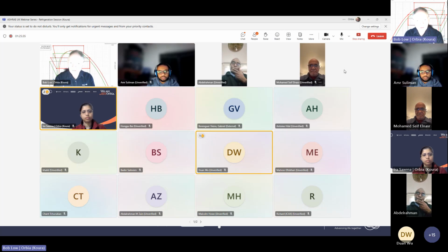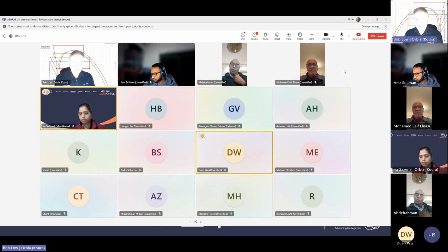The 485A refrigerant has the same sort of lower operating temperature range, about minus 70 C, as 473A does. However, when you look at the compressor characteristics, it would run the compressor extremely hot. So it would require liquid injection cooling, which would take some COP and some capacity away. So although it's attractive, and we are working with one company that's looking at it for minus 70 C, we know quite a few system changes would be needed compared to the current ULT technology, which is basically a cascade of R23 in the bottom or R508 in the bottom into something like R448 or R452A in the top stage. But there are technical solutions. We're working to see if it's a solution that specialized market wants us to bring forward. If they do, then we'll have one there. So again, if you want to know more, get in touch with ERA in the first instance.